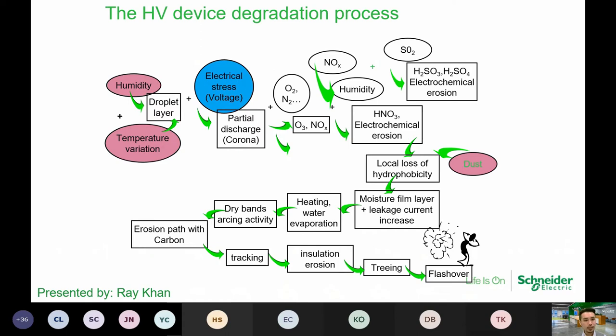So just to very quickly go through, there are a few key components, especially in our region in Singapore. We have a lot of humidity that the switchgear actually experiences, and also a lot of temperature variations. That is where we get condensation, and water droplets start to form. Now, once it comes to the electrical stress, especially coming from the switchgear, that is where corona discharge is actually being issued out. And then that will lead to electrochemical erosion, all right? So you can see in here the chemical formula HNO3. This actually comes in a lot, also when it comes into contact with the buildup of SO2. SO2 is the sulfur dioxide that has been produced from the corrosion process.